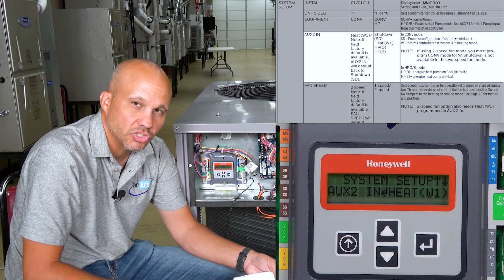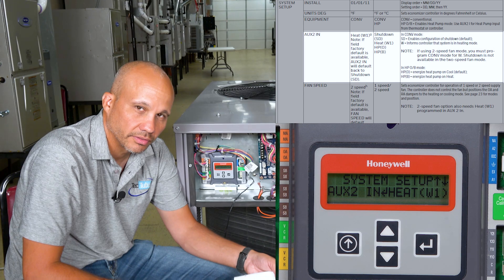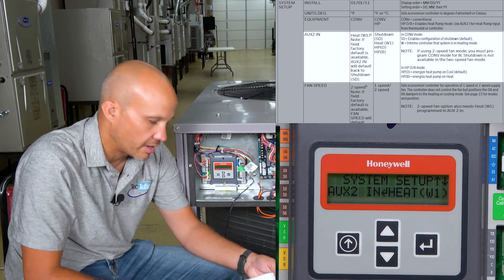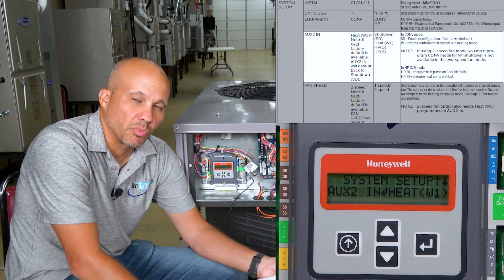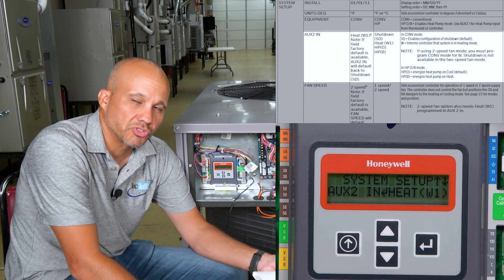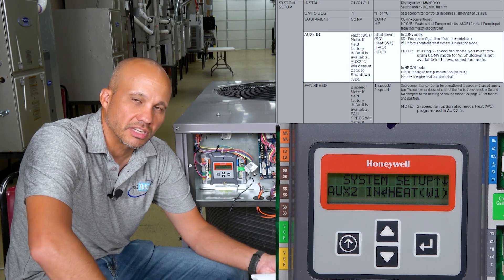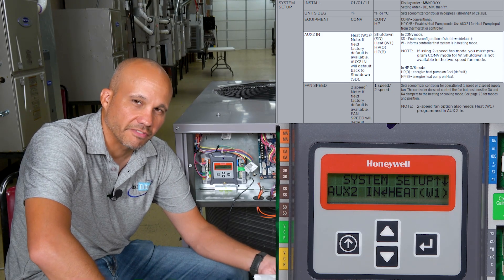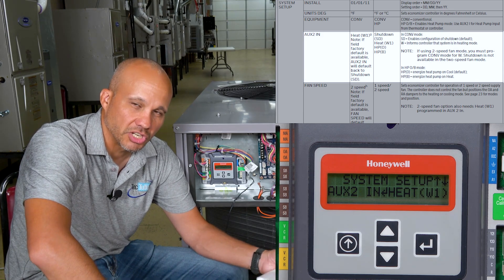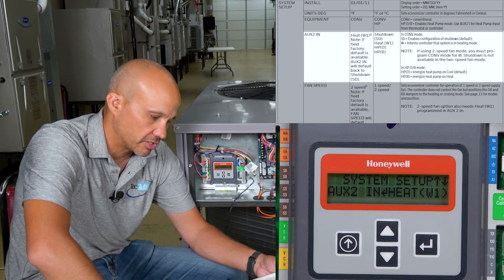It says 'Change Stored' — now I have it set to W1. The reason I'm putting it on W1 is that almost all rooftops are now two-speed fan, which means in addition to the cooling calls Y and Y2 coming to the unit, you also need the W call coming in because the fan speed will change, and hence the minimum ventilation damper position needs to change.